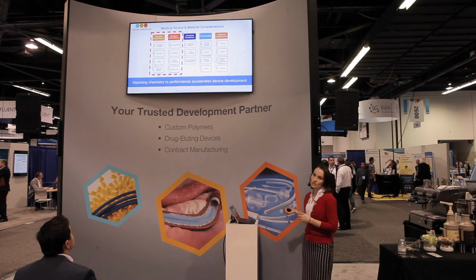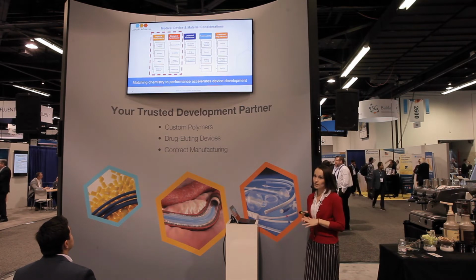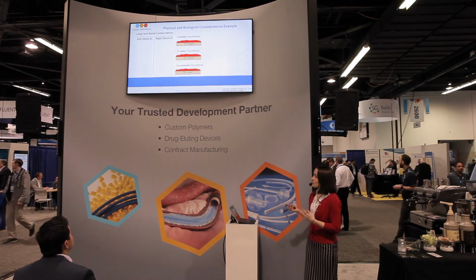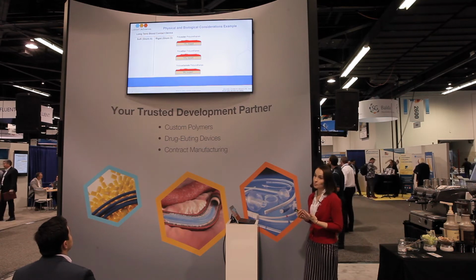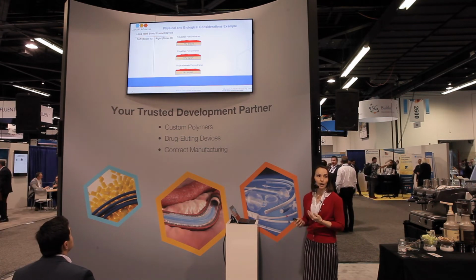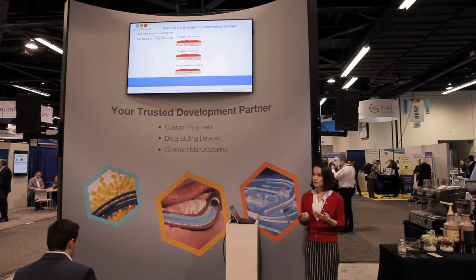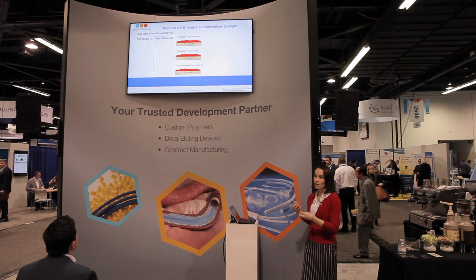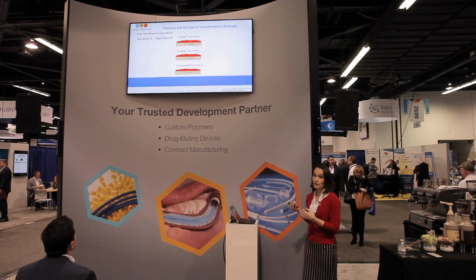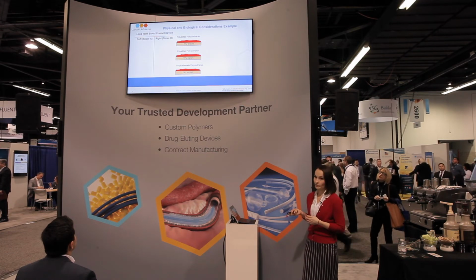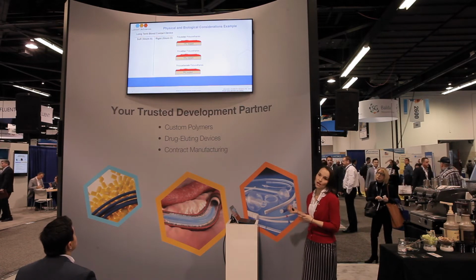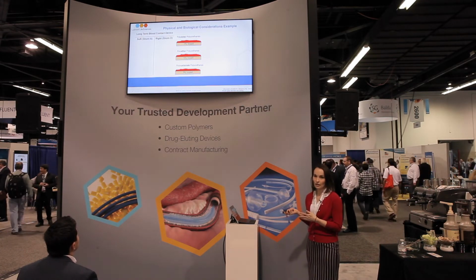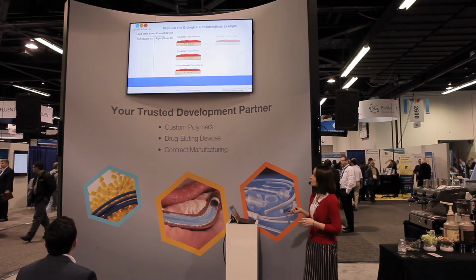The first ones that we're going to talk about include the physical performance criteria along with the biological requirements. The first example is a long-term blood contacting device, and you may want either a softer material that's more flexible. We call those a Shore A hardness material, or a stiffer product that's going to give you maybe a stronger property or a stiffer feel. We'll call those a Shore D material. And up on the screen you see 3 different soft segment chemistries that are available. How would you choose between these chemistries if you're looking for a product for your device?